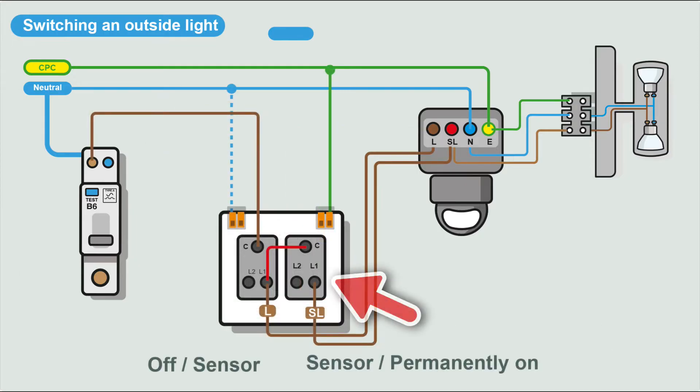To add more functionality, we need to add an extra switch. There's lots of different ways of wiring. Sometimes you get the neutral at the switch, which I've indicated here. You should always have a CPC at the switch. You should run a CPC to every point.